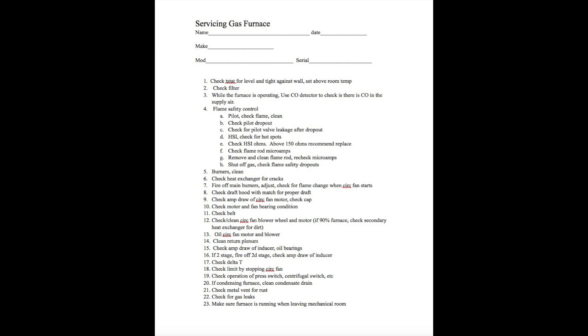Newer furnaces have a hot surface igniter. Check the ohms. Above 150 ohms, recommend replaced. There are different numbers on this, and I'll try to throw a couple of videos up there about that. But check it for white spots. If there's a white spot in it, it means it's about ready to fail or maybe it has failed. If the resistance is above 150 ohms in general, replace.